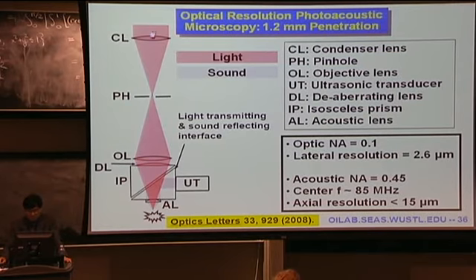So what we do here is to combine the optic axis with the ultrasonic axis. The key component is this device, a light-sound combiner, made of 2 prisms with a gap in between. The gap is filled with a liquid. So the optical refractive index is well matched along the optical axis, but at the interface, the acoustic impedance is mismatched, which means the ultrasound signal will be reflected toward this ultrasound transducer. So we're able to combine the optical and acoustic axes in a single system.